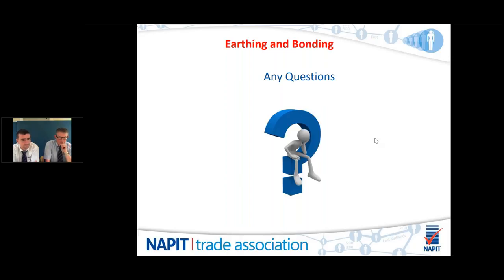So when using 16 millimetre tails, has the size of the earth changed from 10 millimetres? Well, really you should be using 25 mil tails. As long as the tails are large enough to take the currents that the consumer unit connected to it needs, then obviously, to me, you should work to the on-site guide.